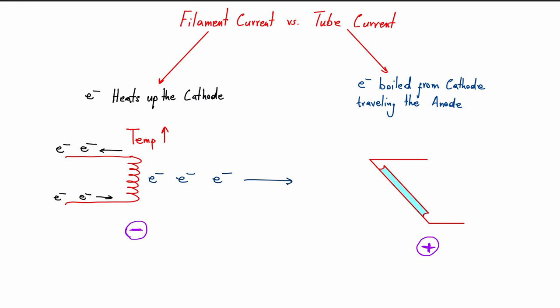Another matter which I want to discuss is the contrast, comparison between filament current and tube current. These two, although seemingly are the same, actually they are not. They are related, more specifically they are proportional to one another, but they are not the same.